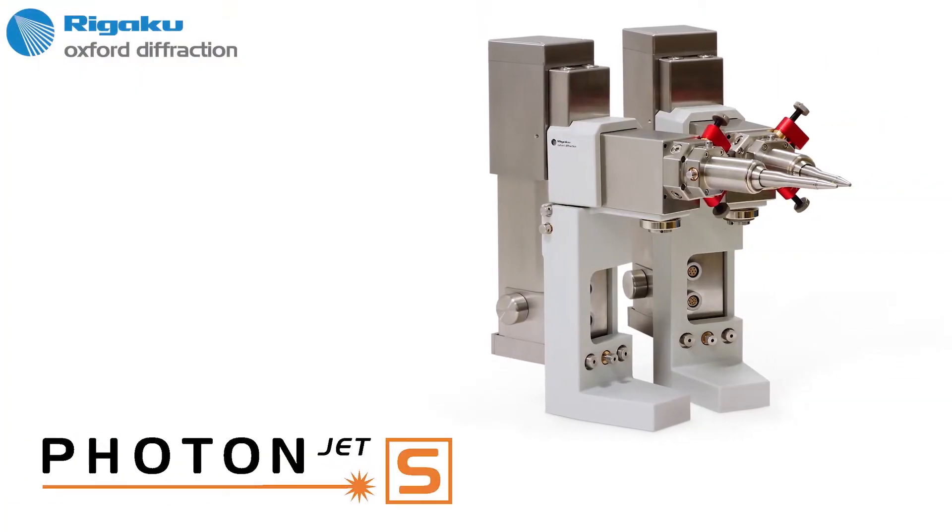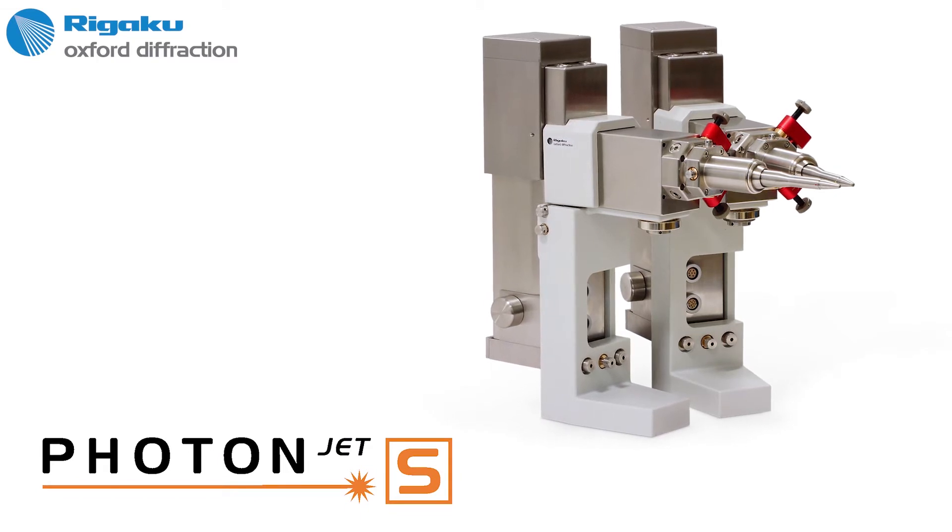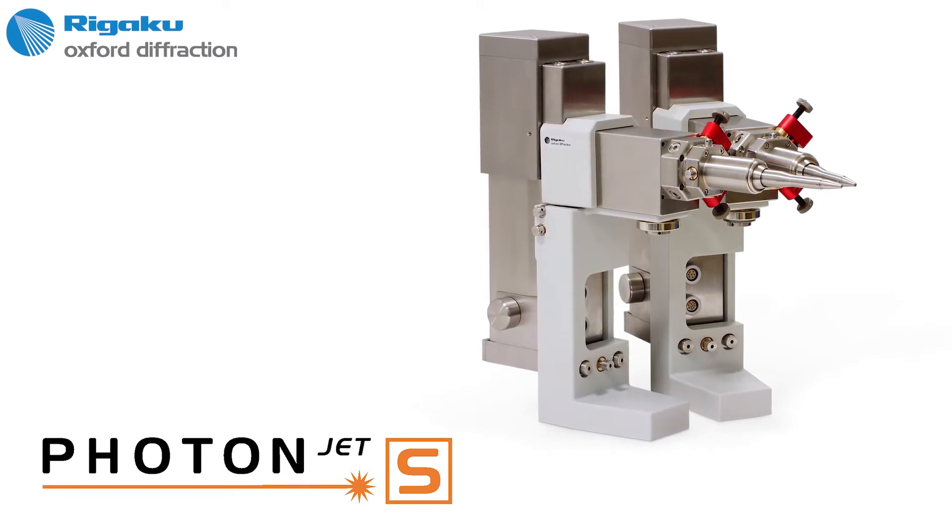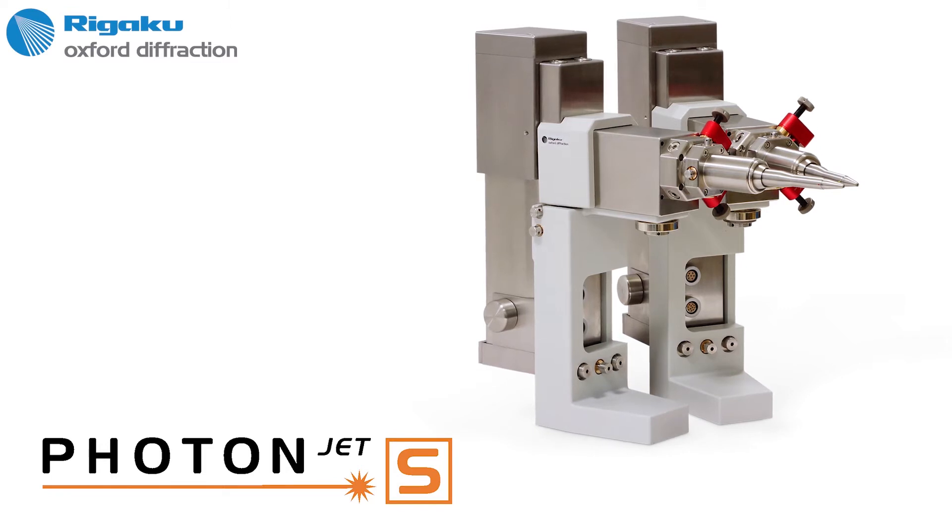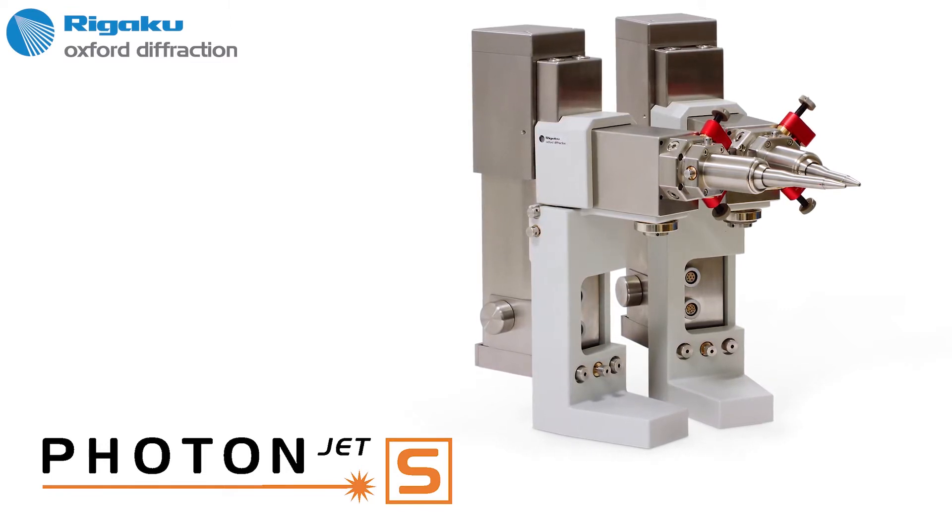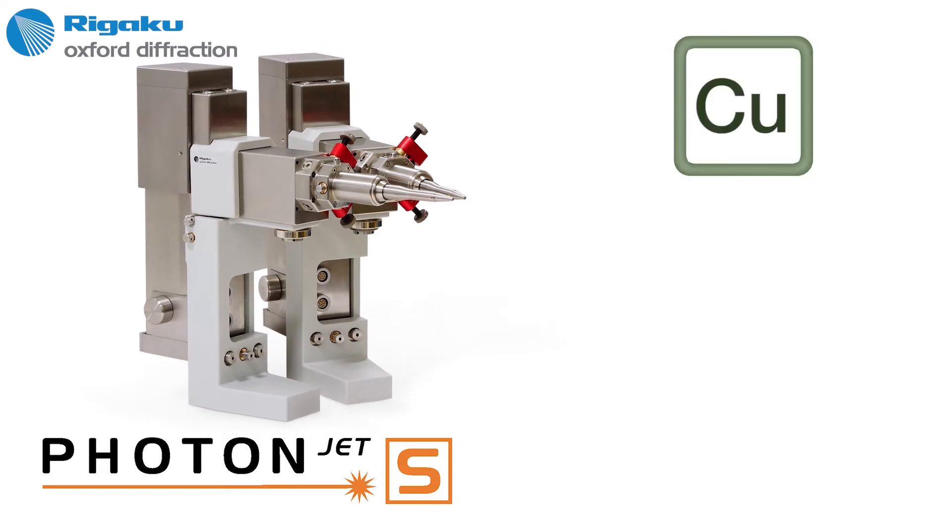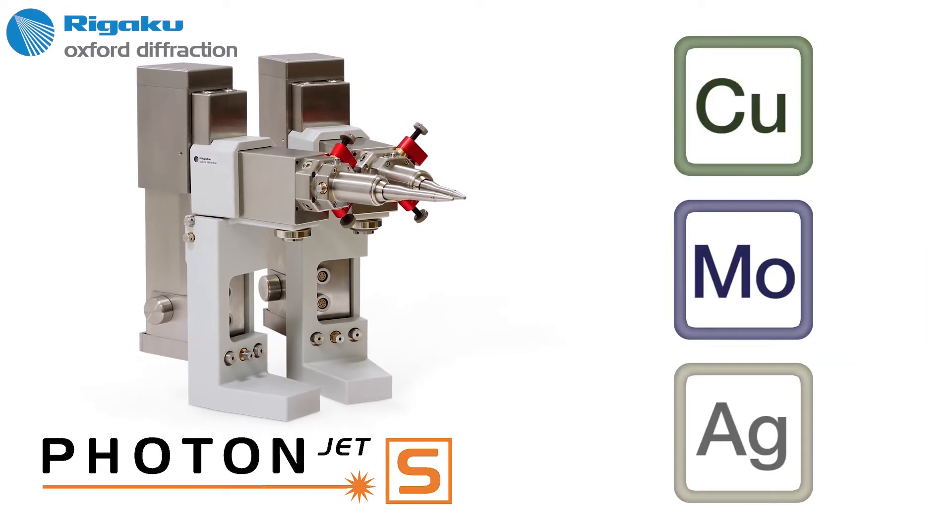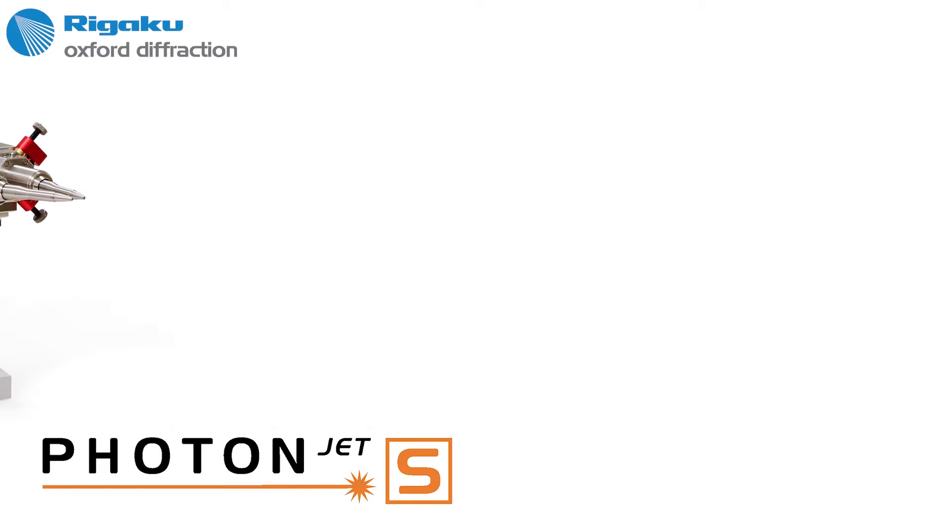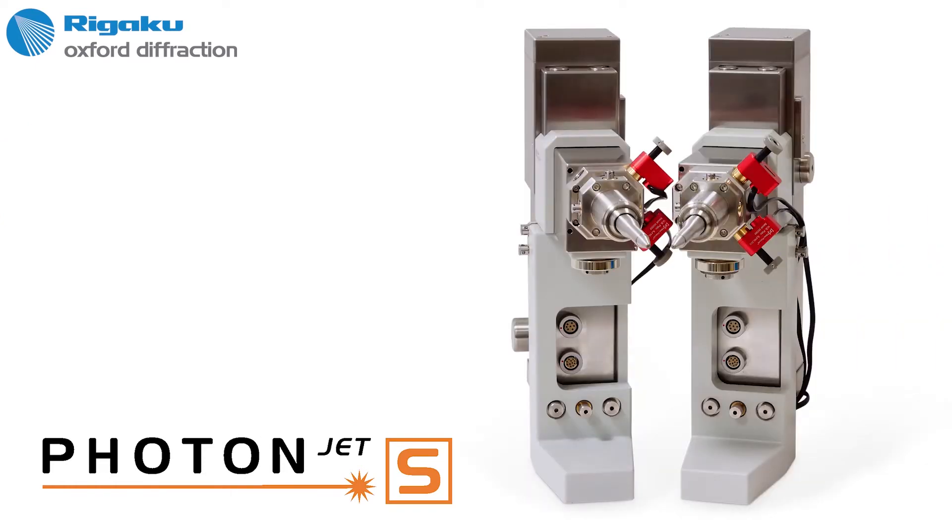Rigaku Oxford Diffraction's brand new microfocus X-ray source, the Photon Jet, is a key component of the XtaLAB Synergy, which can be configured with up to two sources from a selection of copper, molybdenum, and silver. Like its predecessors, the Photon Jet is specifically designed for single crystal diffraction and incorporates new optics and a new X-ray tube design.